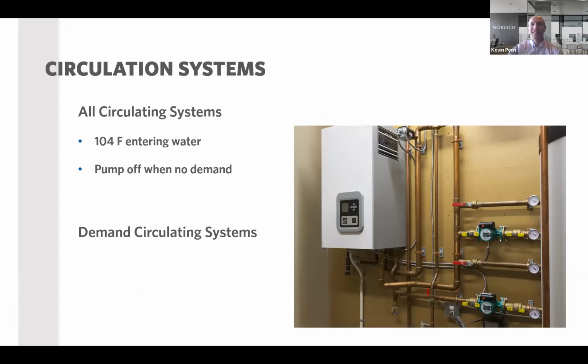Okay, and then the last thing for service water heating, I know that was a long section here, is that they came up with some new things for circulating systems. Not all systems are circulating systems, but they split this up into demand circulating systems and then all other systems. The controls shall limit the temperature of entering cold water to not be greater than 104 degrees. So for all circulating systems, you have to have some type of control set up so that the entering water, basically the water coming back to the heater, can't be more than 104 degrees.